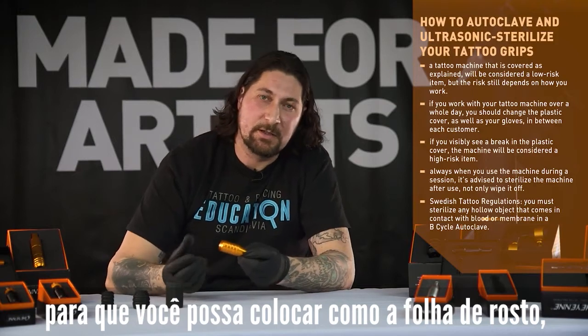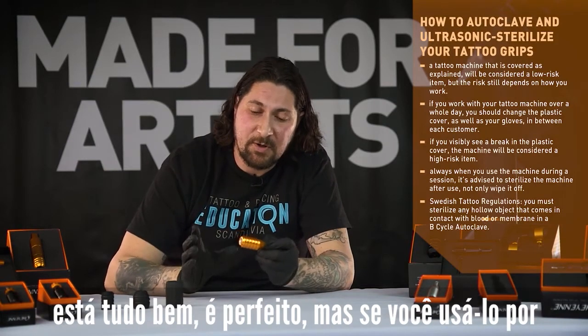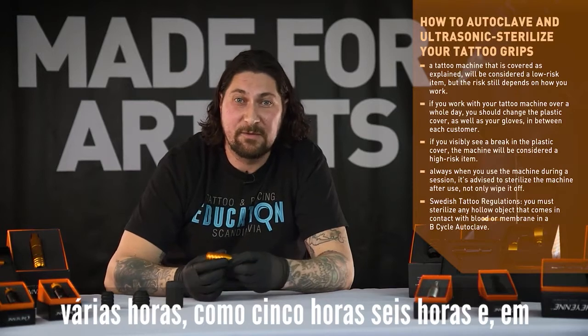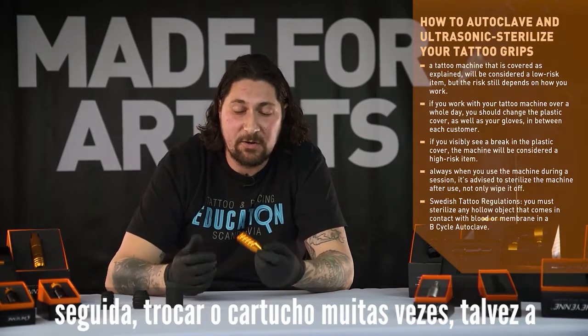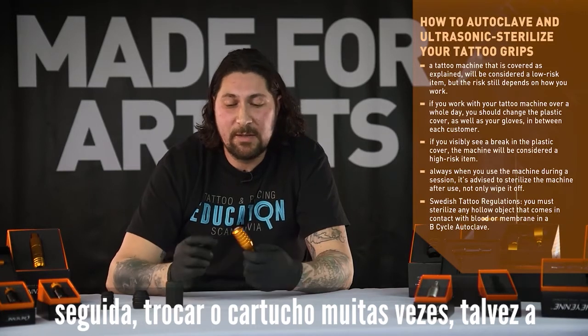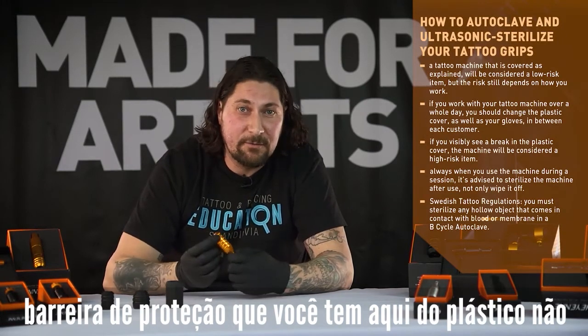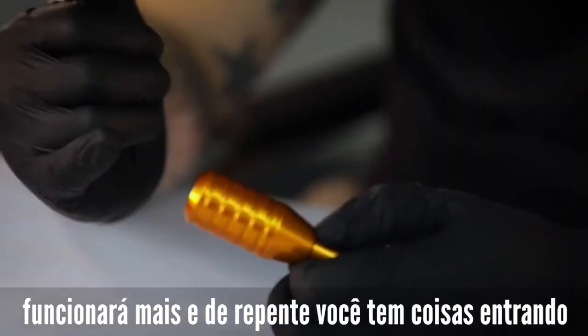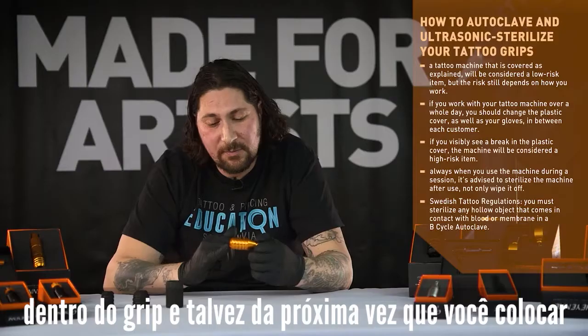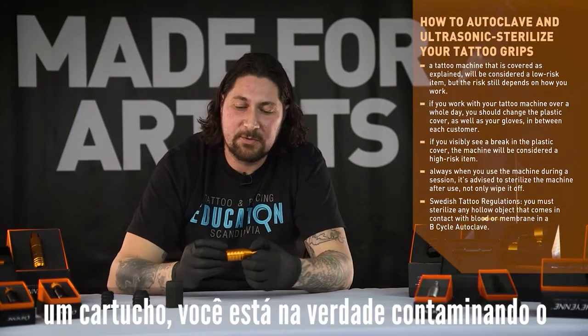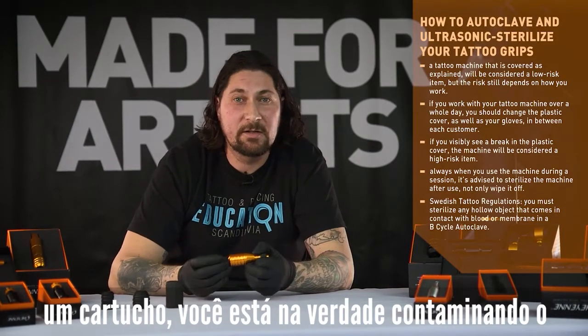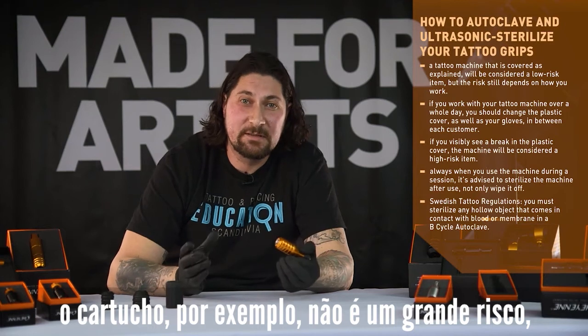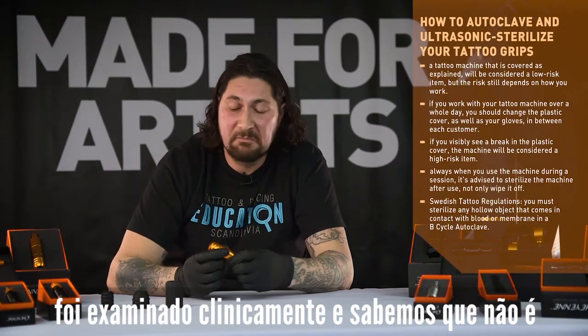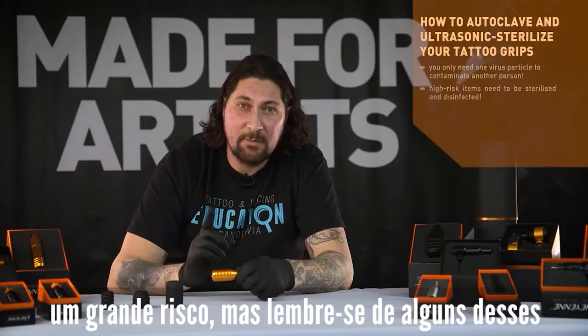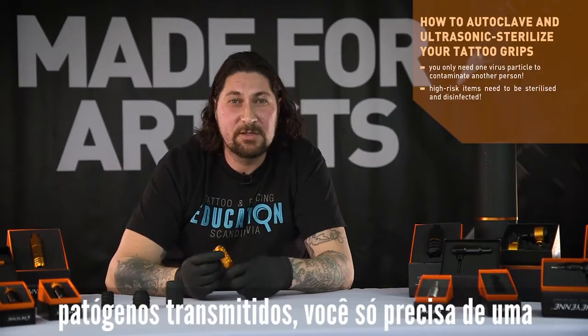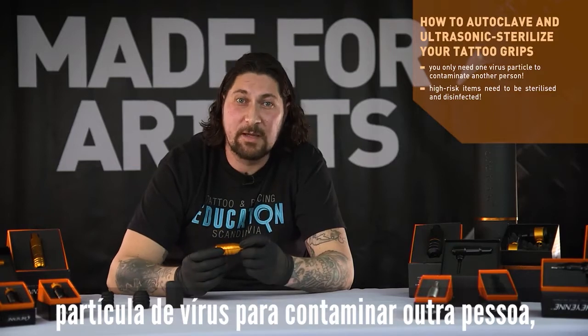So you can put the cover sheet on it, that's okay, it's perfect. But if you use it for several hours, like 5 hours, 6 hours, and then change the cartridge many times, maybe the protection barrier that you have here from the plastic won't work anymore, and all of a sudden you have stuff coming in the inside of the grip, and maybe next time when you put a cartridge in, you're actually contaminating the cartridge, for example. It's not a big risk. It's been looked at, medically tested. We know it's not a big risk, but remember, for some of these bloodborne pathogens, you only need 1 virus particle to contaminate another person.